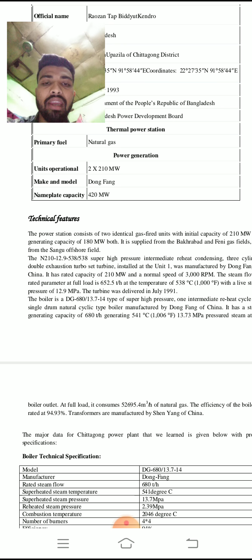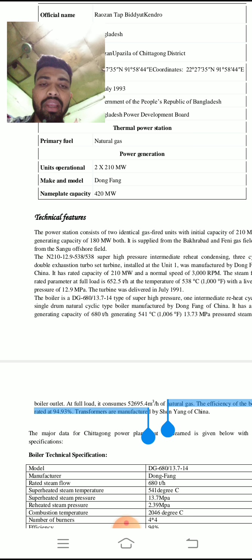It has a rated capacity of 210 megawatts and a normal speed of 3000 rpm. The steam flow at rated parameters of fuel is 652.5 tonnes per hour at a temperature of 538 degrees Celsius, with a live steam pressure of 12.9 megapascals. The turbine was delivered in July 1991.